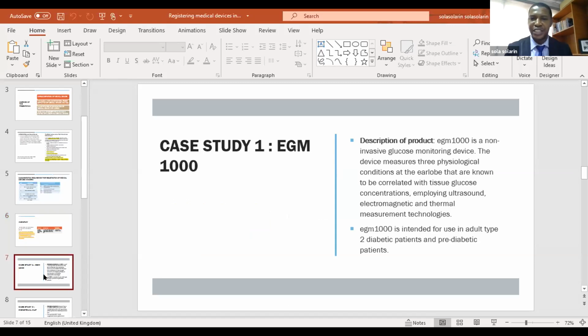So the first case scenario, which I'll be sharing, is the EGM 1000. Basically, the EGM 1000 is a glucose monitoring device, but in this case, it's non-invasive. It takes the blood glucose level employing ultrasound technology, electromagnetic technology, and thermal measurement. As you could see in slide 5, while we were registering this product, we put together those sets of 11 documents and we submitted to NAFDAC because the NAFDAC guideline only prescribed those sets of documents.